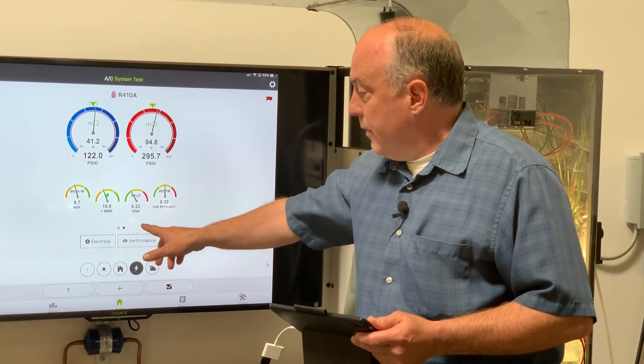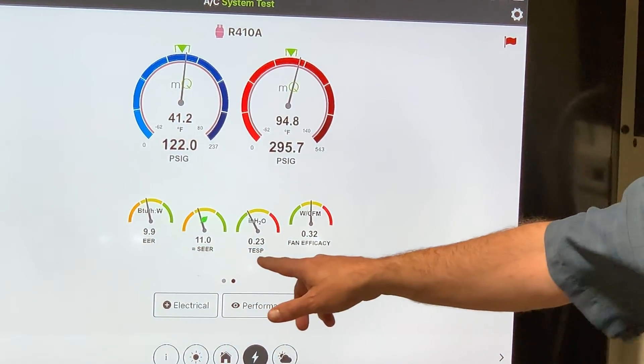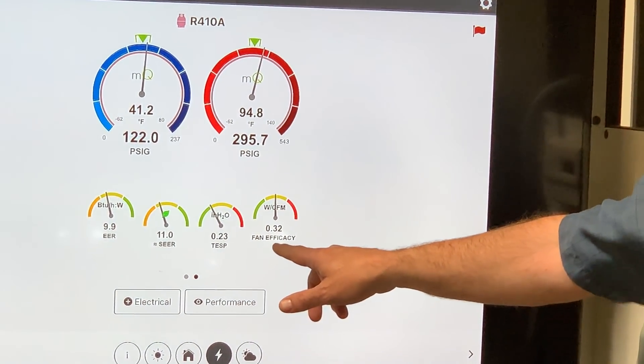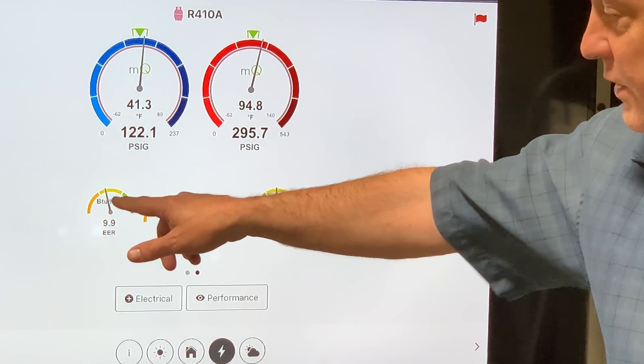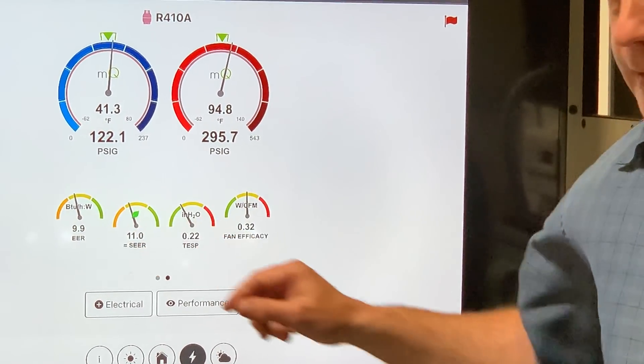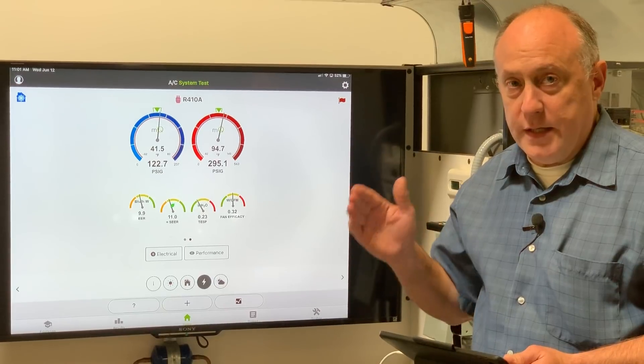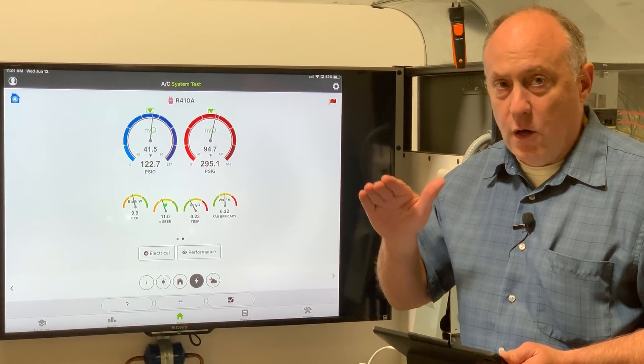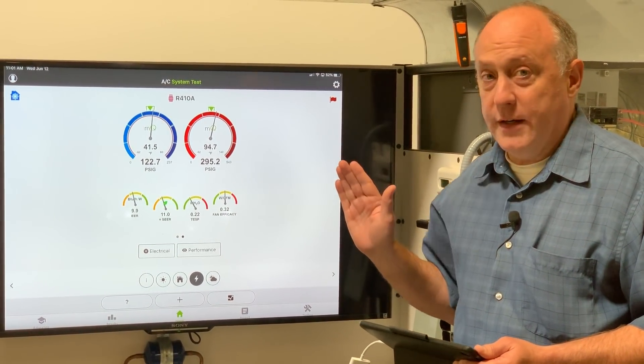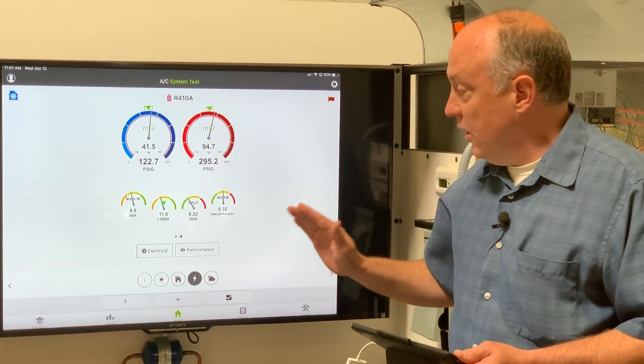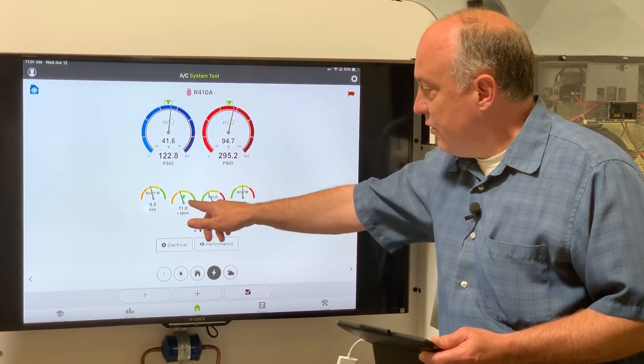Right now we're on a performance screen here, and we can see that we have EER, SEER, total external static pressure, and fan efficacy. From yellow to green, these are simply low efficiency to high efficiency. When you're in the yellow zone, you're in the lower efficiency zone. When you're in the green zone, you're in the higher efficiency zone. And you can see right now we're in that mid efficiency range.